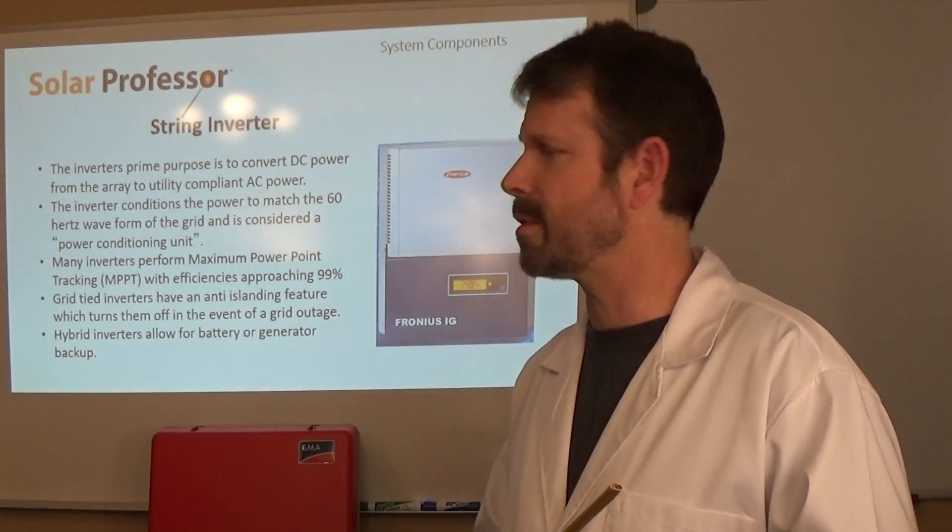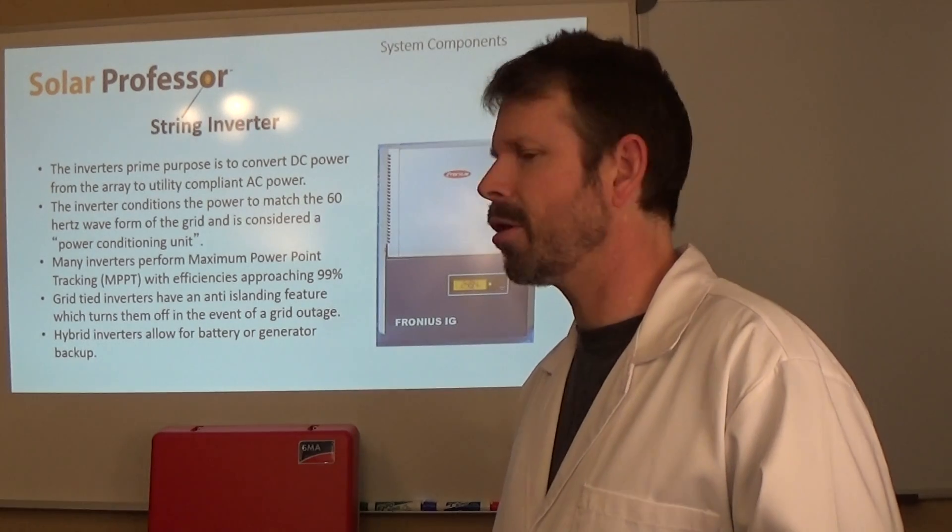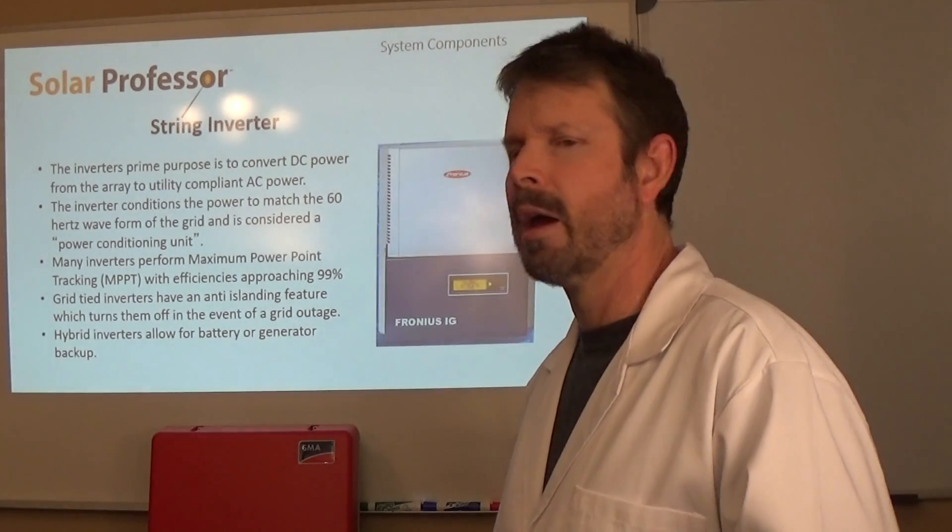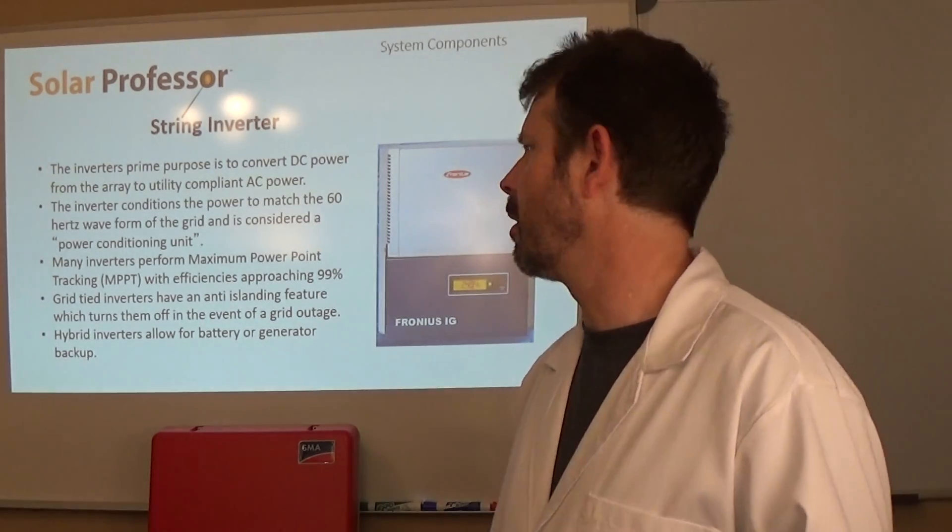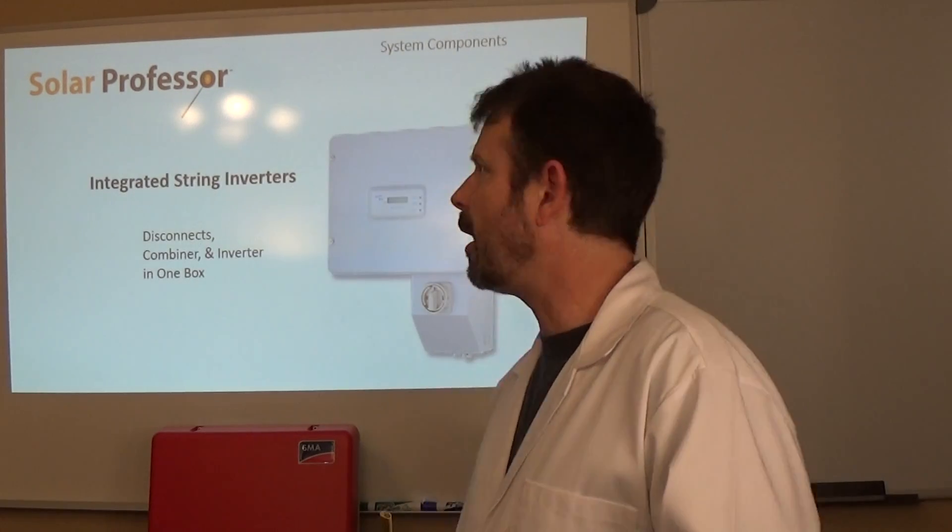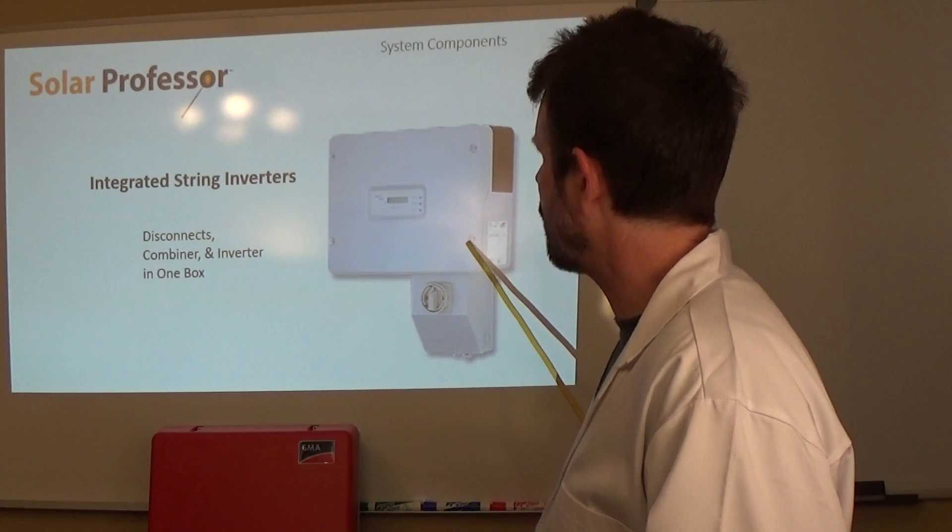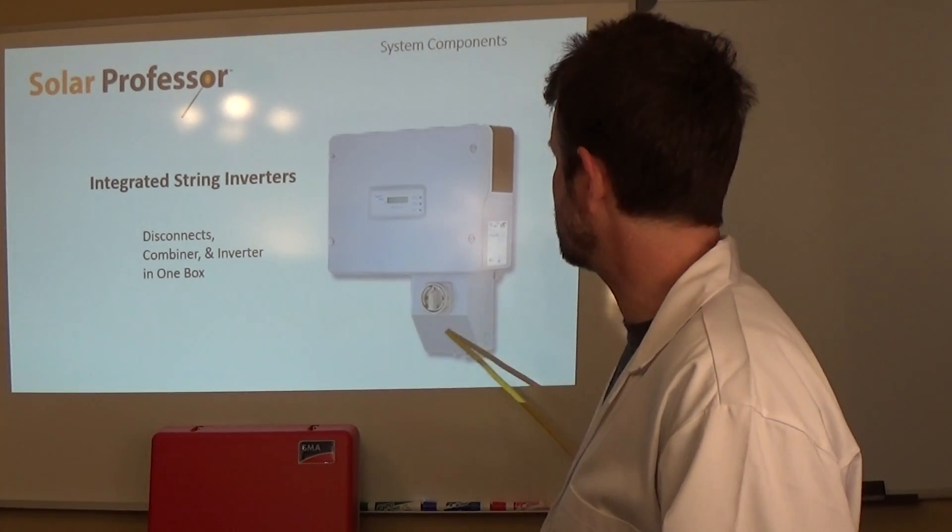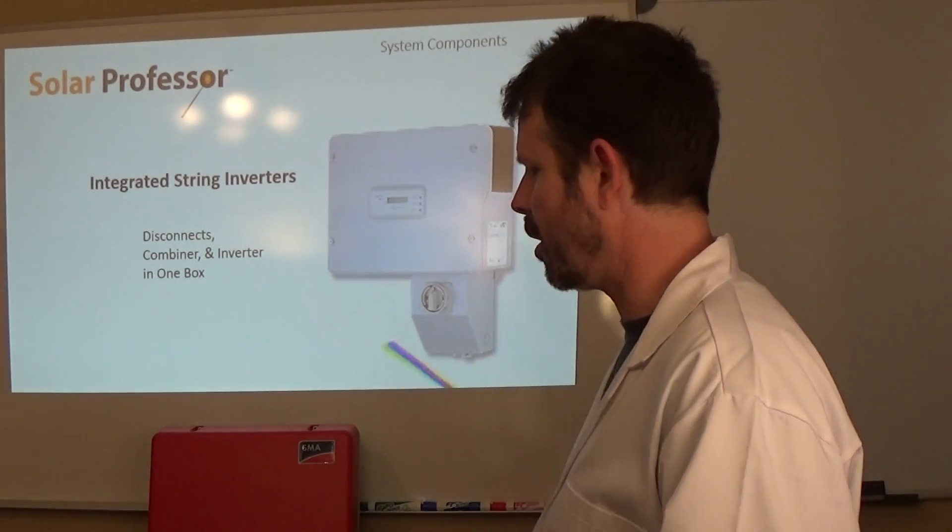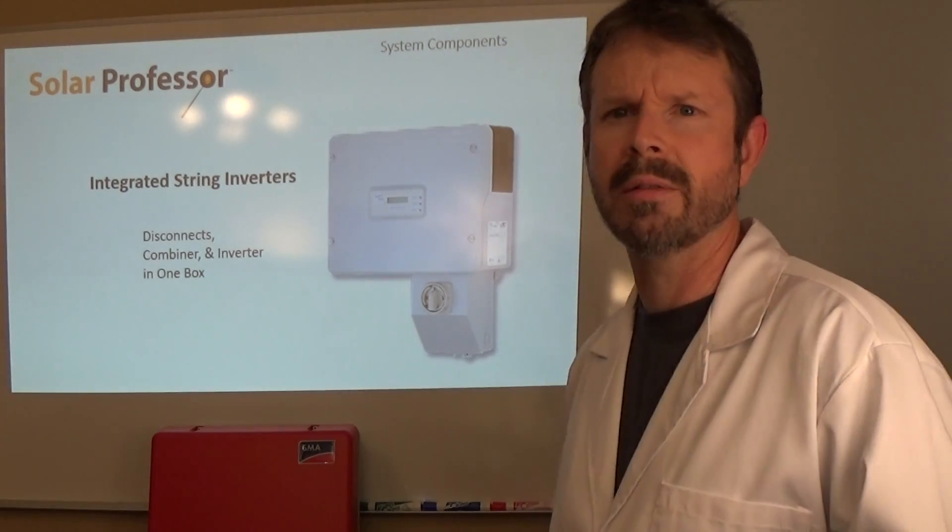If we're setting up a bimodal system, the whole point of that is to have a battery backup along with it and then your system will continue to operate. If it is a complete off-grid system of course it's going to continue to work if the power grid goes out. The standard utility interactive system which is directly just connected to the power grid will actually shut off if the power goes out. Very important to note that and mention that to your customers. Hybrid inverters allow for battery or generator backup. Here's an integrated string inverter, this is an SMA brand, it has a disconnect and combiner box built right in, all in one unit.